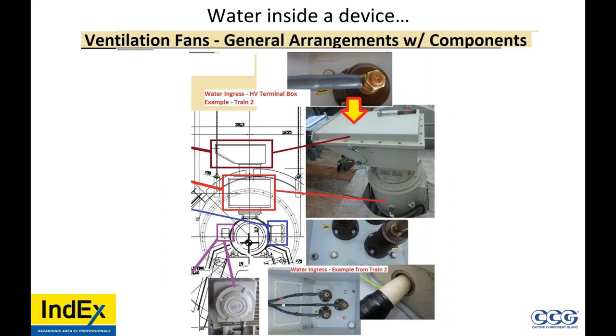water ingress to devices. We're told in the hazardous area industry that ingress protection does not matter when it comes to the EX protection technique. This is a high voltage motor, 6,600 volts. Now, if you take a look in the bottom right, you can see all the condensation in there, but also in there, there's puddles of water within a high voltage terminal box. Now, the bolts inside don't have IP washers, so water is now going down into the motor.